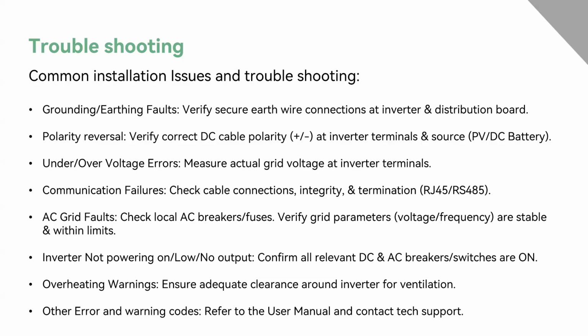If we cannot power on the inverters, or there is no output, we have to confirm all the relevant DC and AC breaker switches, also the switches on the side of the inverters, the power on and the EPS switches. For overheating warnings, we have to make sure that there is adequate clearance around the inverters for ventilation. About other errors and warning codes you see on the inverter LCD or on your app, you have to refer to the user manuals for detailed troubleshooting. Also, you can contact our tech support team.